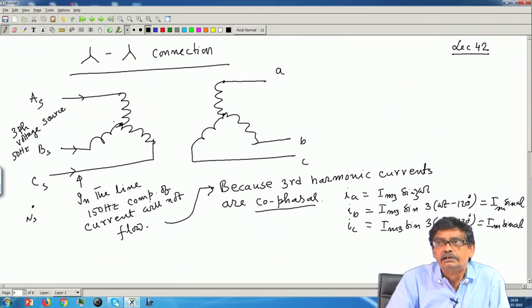So, they are cophasal, meaning that if third harmonic current flows here, at any instant if this current going this way is 5 ampere, this will be also 5, this will be also 5 ampere, and they will meet here, they will not vanish, KCL will be violated, which is not the case with the fundamental component. Fundamental component, suppose the instant when the A phase current is maximum positive, say 10 ampere, then B and C will be minus 5, minus 5. So, it will return via this path.